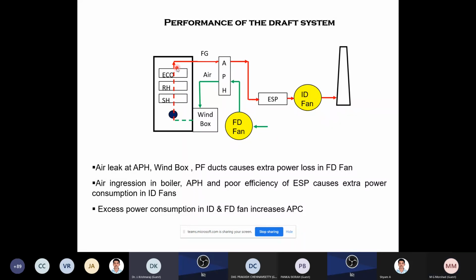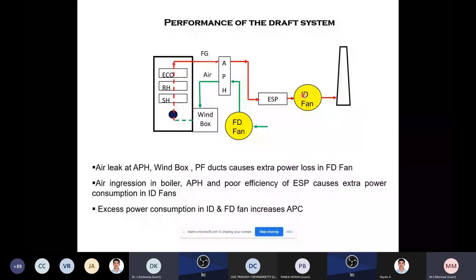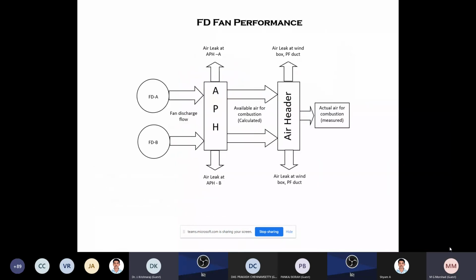So that is why, to avoid unnecessary loading of the ID and FD fans, the air leaks should be arrested. Before that, you have to identify how much excess power the ID and FD fans are taking, and what the fan performance is. This is a very important thing for the draft system. Okay. Now just see, there are two FD fans, then the air heater, then combustion will be calculated. From the air heater, it will be the actual air for the combustion.